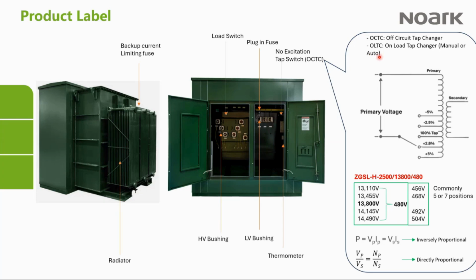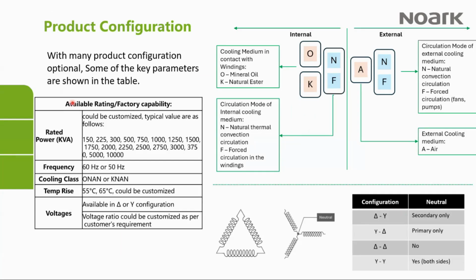So that's the difference. We also have what you call the auto tap changer. In the case of an auto tap changer, you don't even need to physically go there. It's automatic. It self-regulates. When the voltage drops, it compensates, and when the voltage increases, it will compensate too, just to ensure that you're constantly getting the voltage you need on the secondary side. So that's why we need a tap changer.